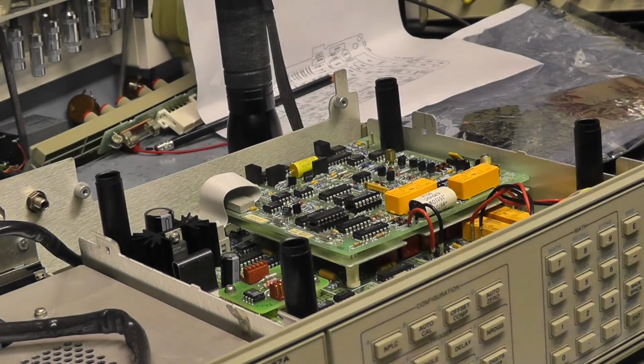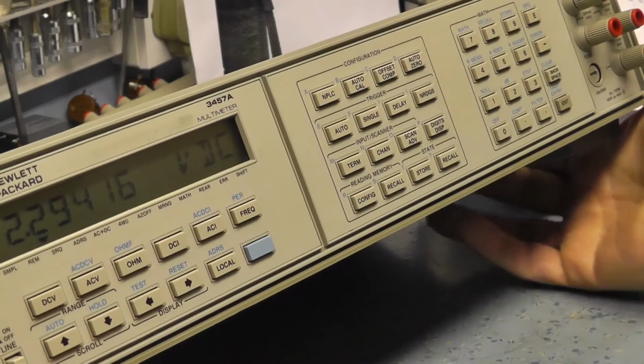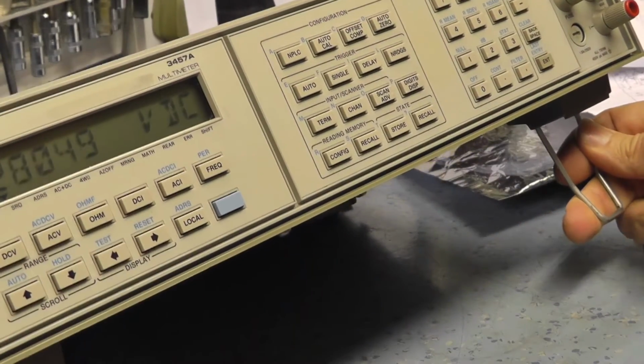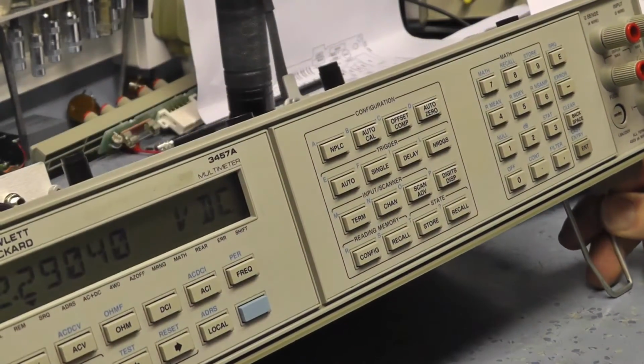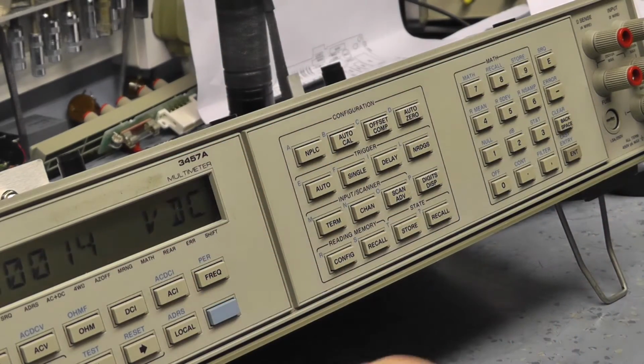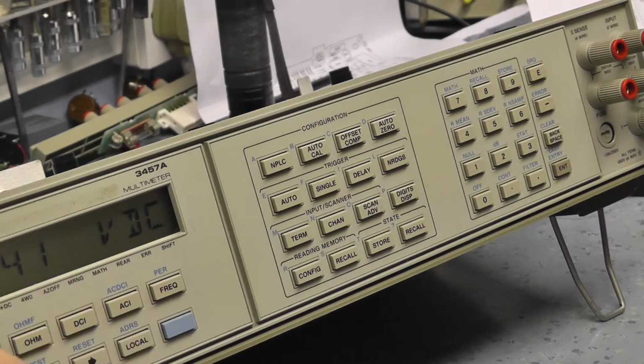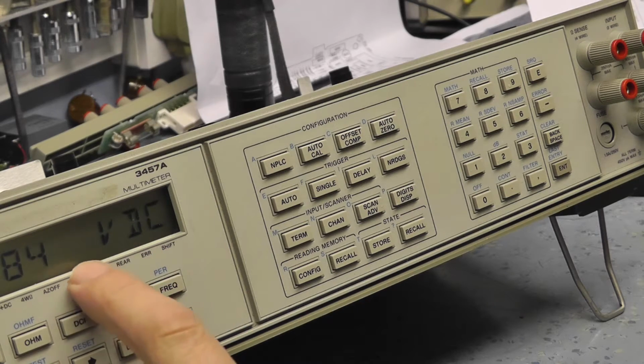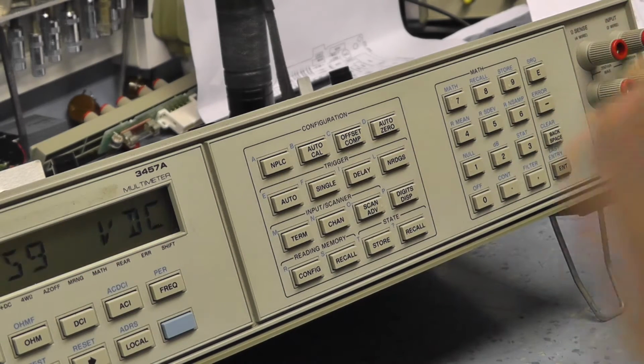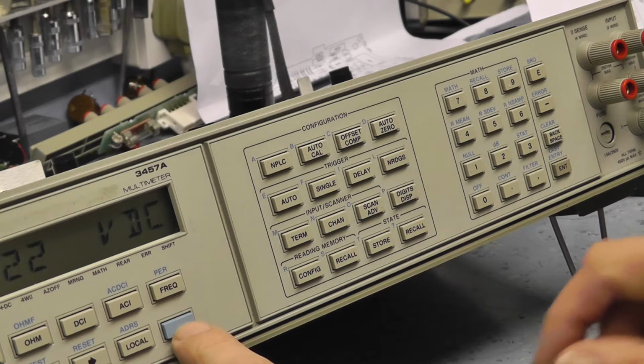The only problem is the meter is still showing this error message on startup. That could be a number of reasons. I've performed a calibration on this now. If you remember, one of the calibrations was to try and set the zero offset with the trimming capacitor. That was on the previous video, and I'll just try and demonstrate that now.